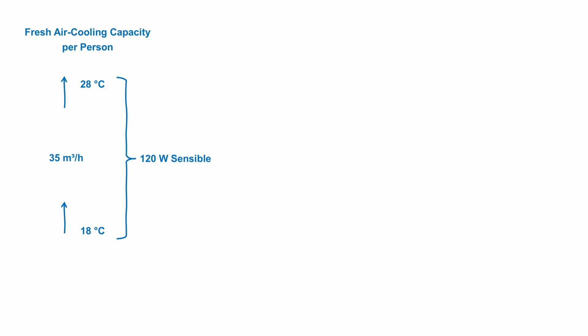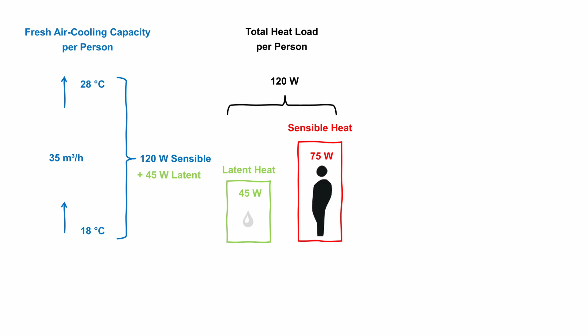The latent heat raises the humidity in the air but does not increase the air temperature, as it is carried away in vapor form. The fresh air system is therefore designed to handle up to 120 watt sensible load plus 45 watt of latent load per person. This means that beyond offsetting the person's 75 watt sensible load, the fresh air also provides roughly 45 watts of additional sensible cooling load to the space.